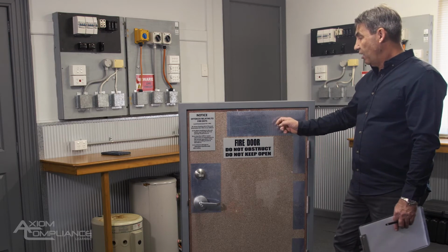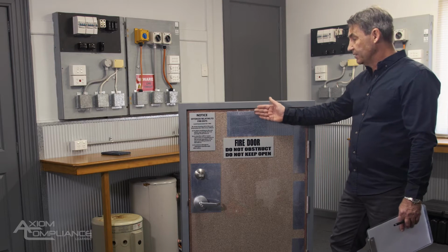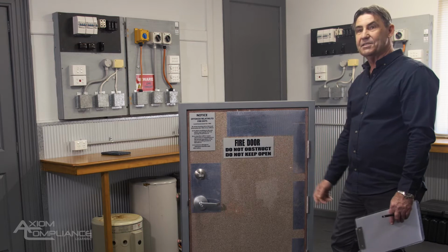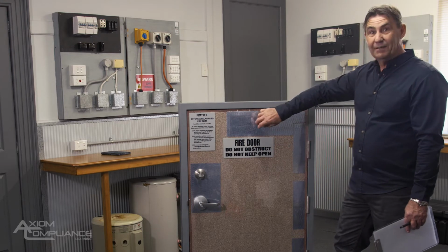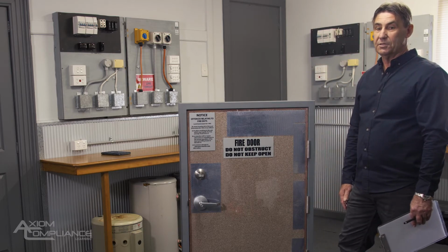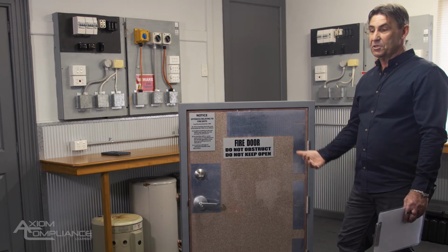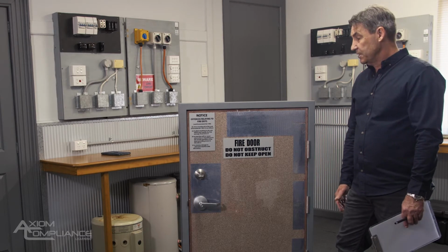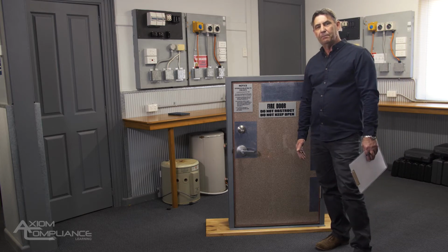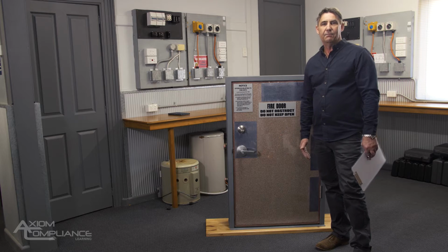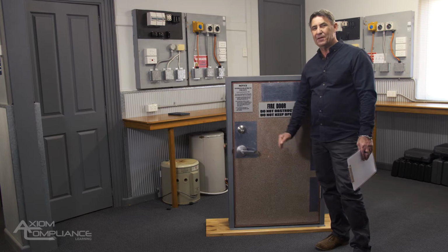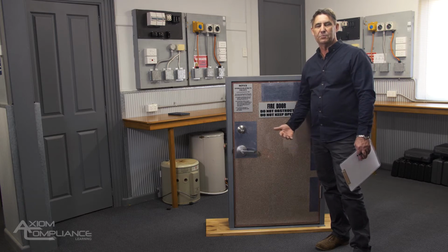And so oftentimes, if you're looking at a door that's laminated, you won't obviously see these plates that are in the door. And so we can use a magnet, and we put a magnet around the door on those places to see whether the door is actually a fire door or not, because it just looks like a normal door in most circumstances. So we need to establish that the door hasn't been modified since the last inspection, and you may want to compare this door to other doors that are in the installation. And as I said before, it's generally the hardware that's going to indicate whether the door's been modified.